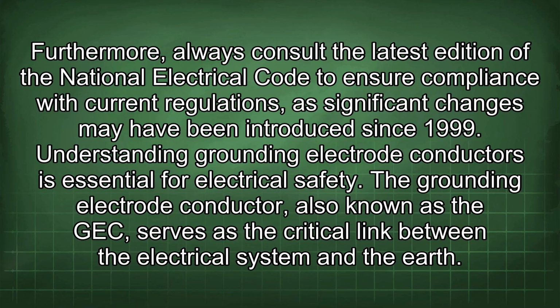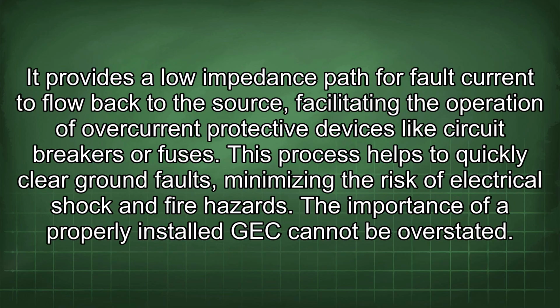Understanding grounding electrode conductors is essential for electrical safety. The grounding electrode conductor, also known as the GEC, serves as the critical link between the electrical system and the earth. It provides a low impedance path for fault current to flow back to the source, facilitating the operation of overcurrent protective devices like circuit breakers or fuses. This process helps to quickly clear ground faults, minimizing the risk of electrical shock and fire hazards.